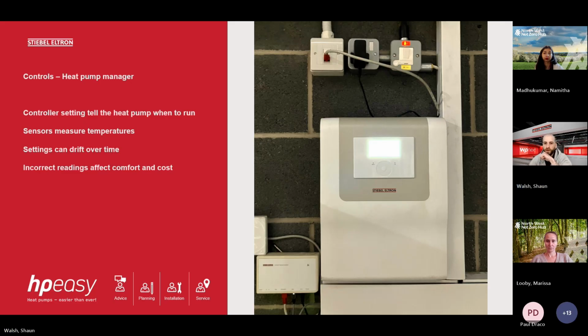Okay. So it's more about checking that the system understands what is happening within the building and what's actually happening outside, rather than looking at all the different settings and parameters. We just want to know that the controller understands what's happening outside and what is happening inside the building. And you can do that relatively easily inside the heat pump manager.